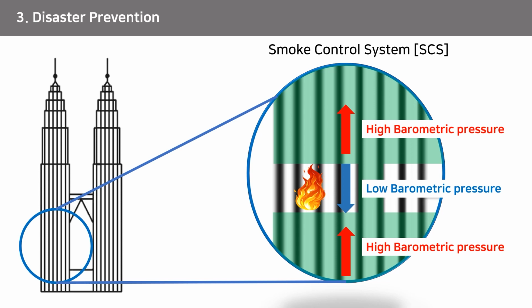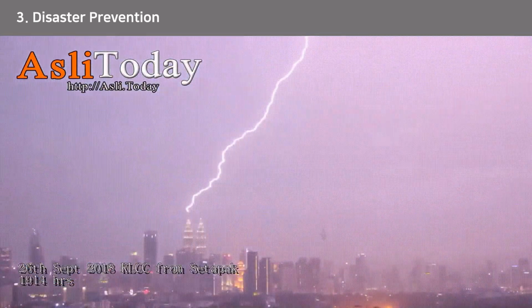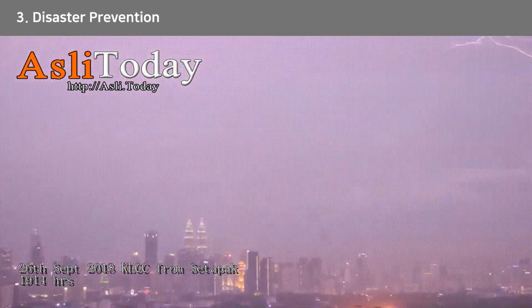This ensures that the air pressure on the floor where the fire broke out is relatively lower than that of the other floor spaces and the elevator passage on that floor, thereby inducing smoke to be blocked and discharged from the floor. In addition, the air on all floors except the floor where the fire alarm occurred is adjusted to support the daily activities of occupants on other floors not affected by the fire. This video is part of a direct lightning strike at the Petronas Twin Towers.